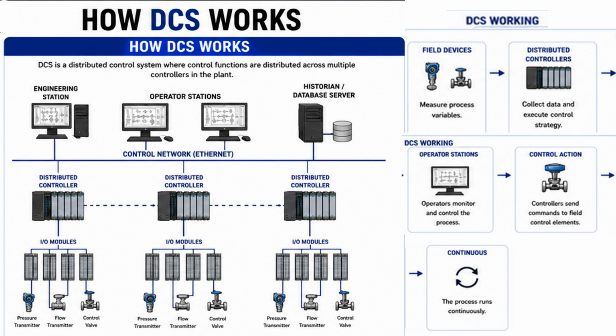DCS section. DCS stands for Distributed Control System. The keyword here is distributed. Instead of using one central controller, the control is divided among many controllers. Each controller manages a specific part of the process. One controller may supervise the boilers. Another controls the cooling system. Another controls pumps. Another manages compressors.